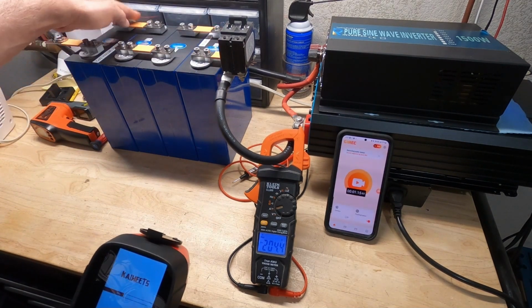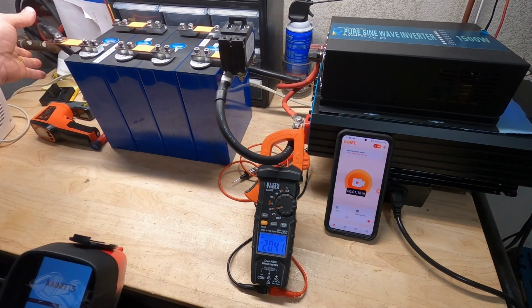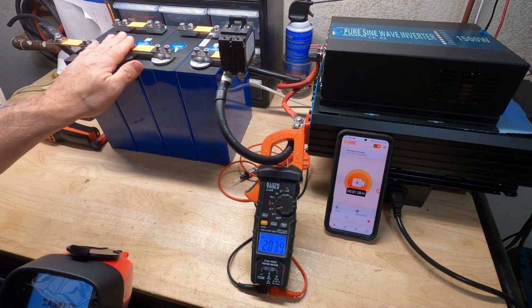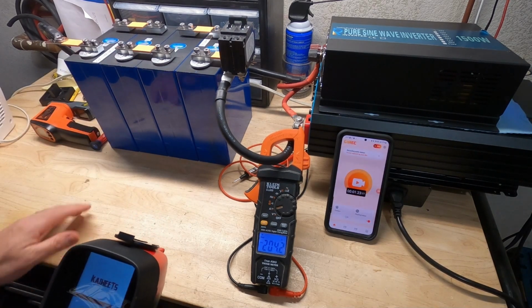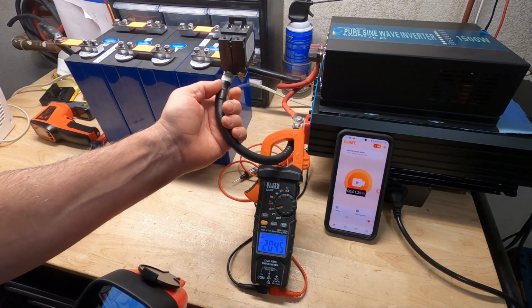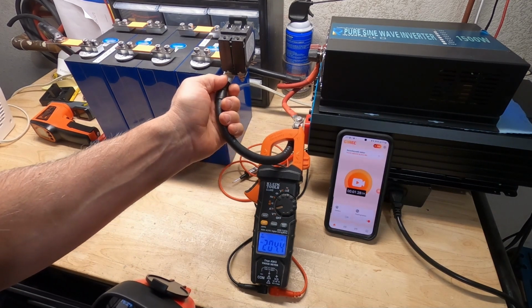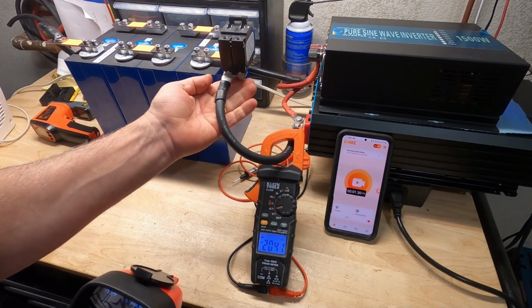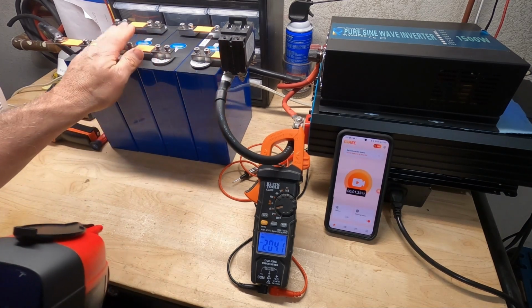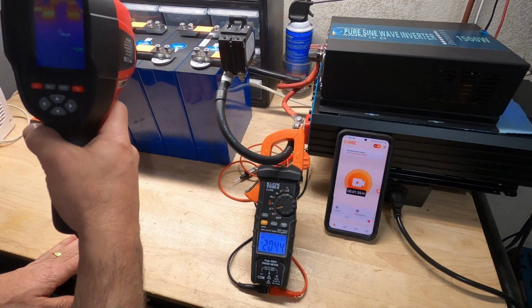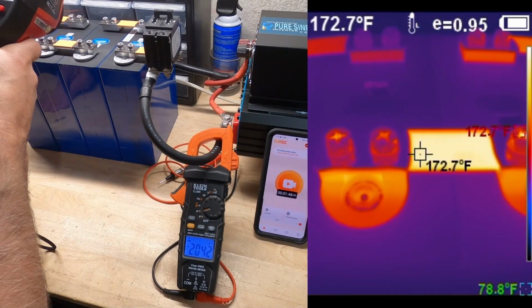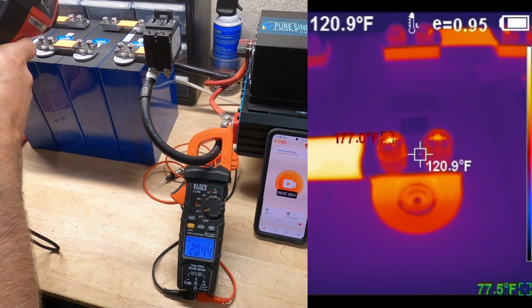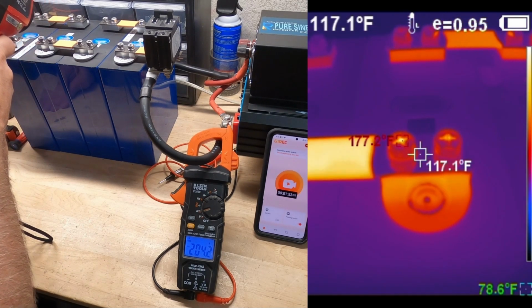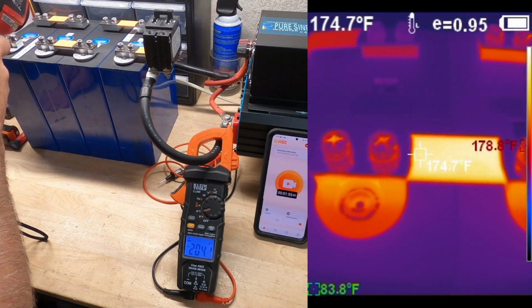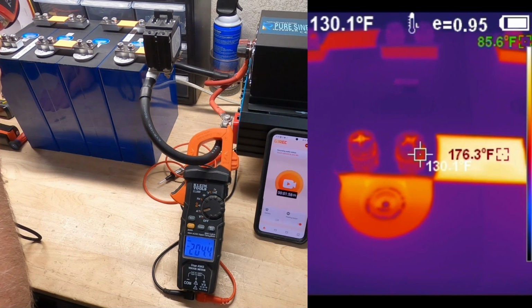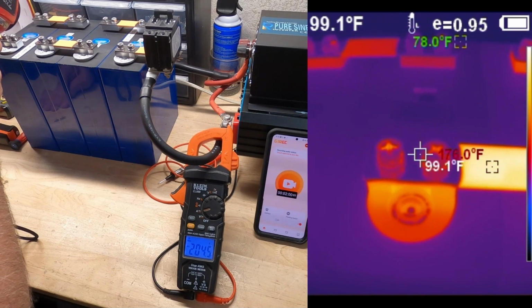These terminals are already quite warm. Oof, yeah. Those are warm. But the cable is actually pretty cool to the touch. The terminals are definitely hot. So these are the double stud terminals, sitting at about 130 degrees. Inverter fan turned on, 170 degrees on the stud there.